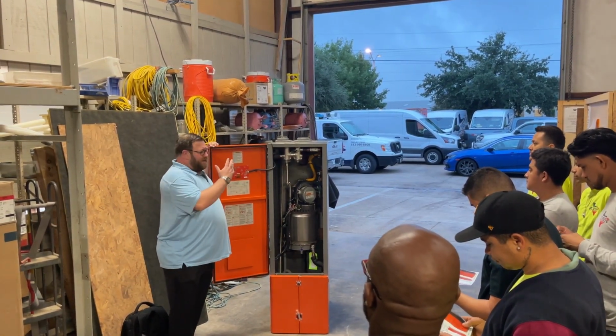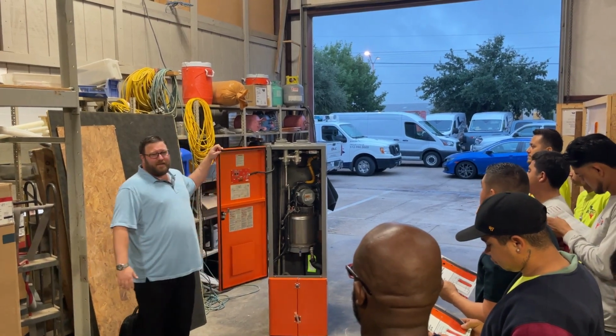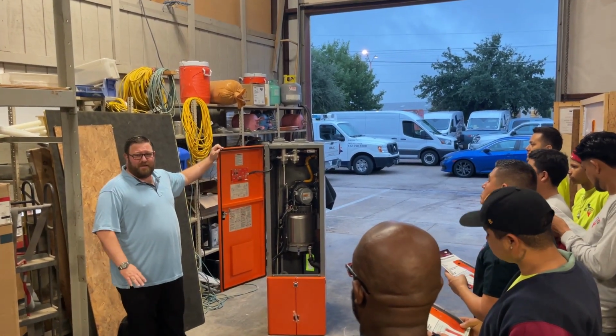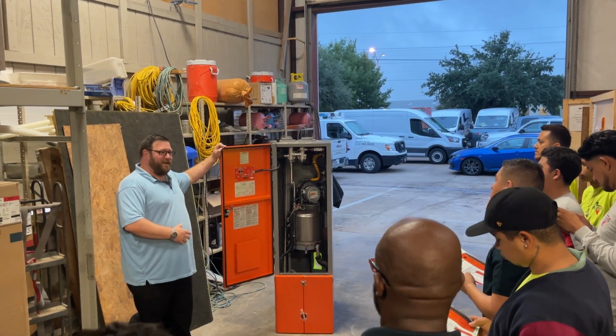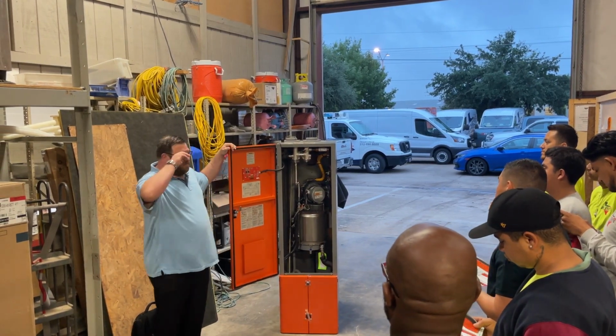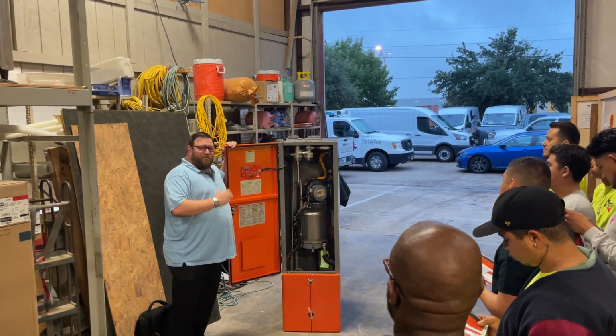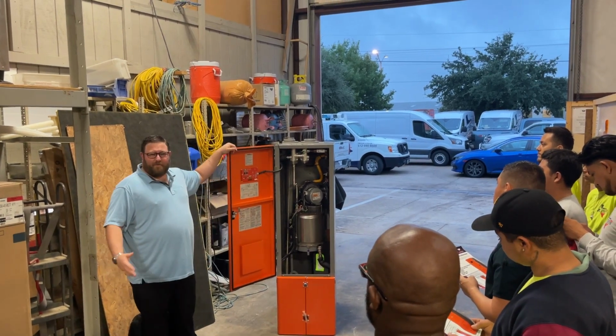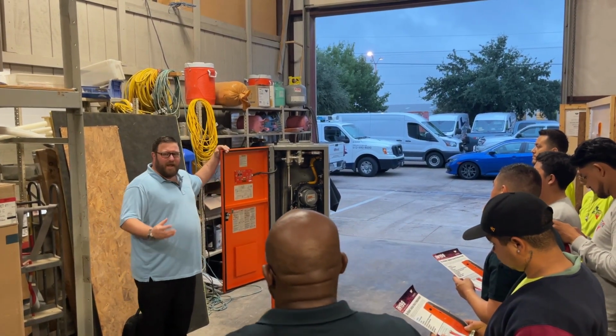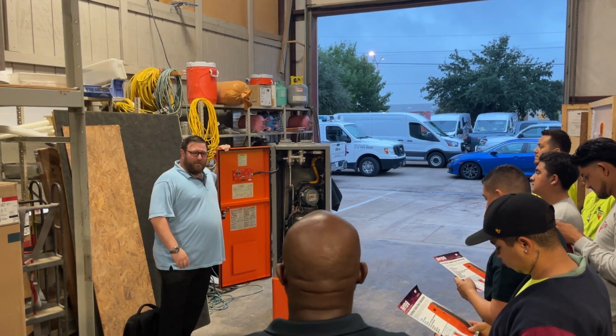As plumbers, you say this thing can do 15 gallons a minute just like a tank. I say no, and I add, neither can a tank. Then you say yes it can, and I say no it can't. We go back and forth, but the fact is, if you do 15 gallons a minute with a tank, after 3 or 4 minutes it's already tempered water, and now you have to recover that water to get back to hot.